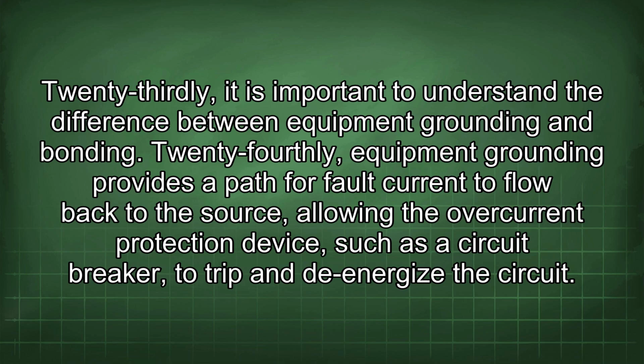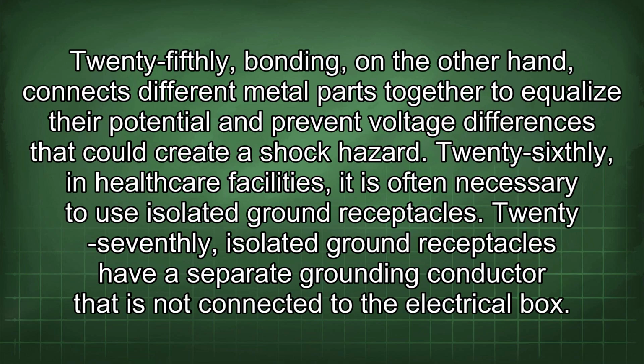Twenty-thirdly, it is important to understand the difference between equipment grounding and bonding. Twenty-fourthly, equipment grounding provides a path for fault current to flow back to the source, allowing the overcurrent protection device, such as a circuit breaker, to trip and de-energize the circuit. Twenty-fifthly, bonding, on the other hand, connects different metal parts together to equalize their potential and prevent voltage differences that could create a shock hazard.